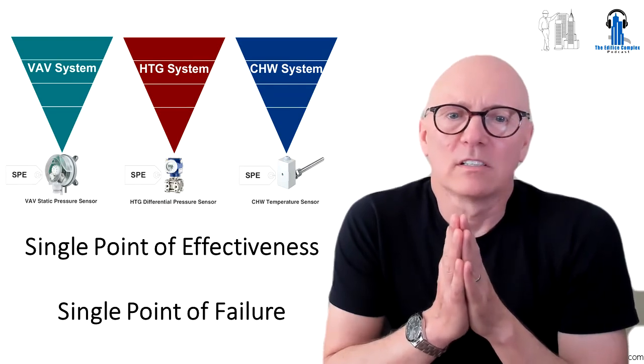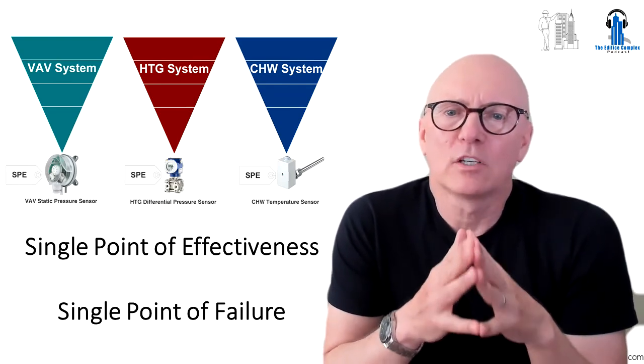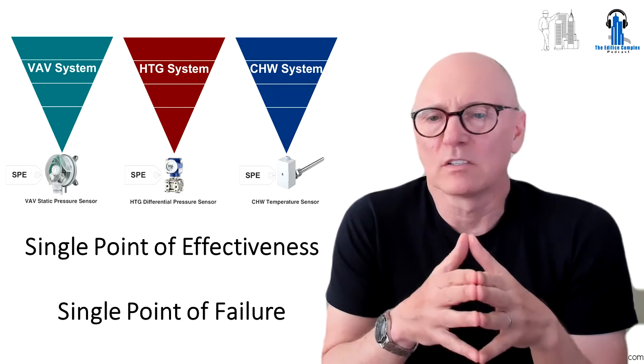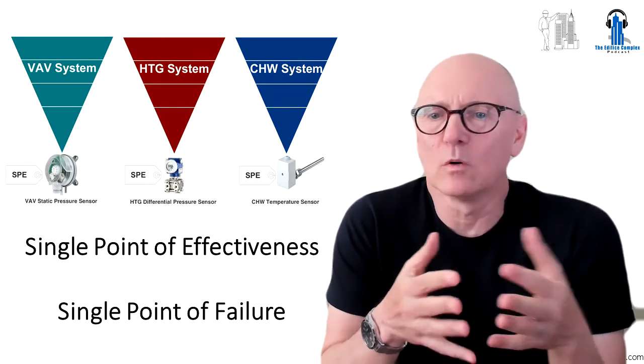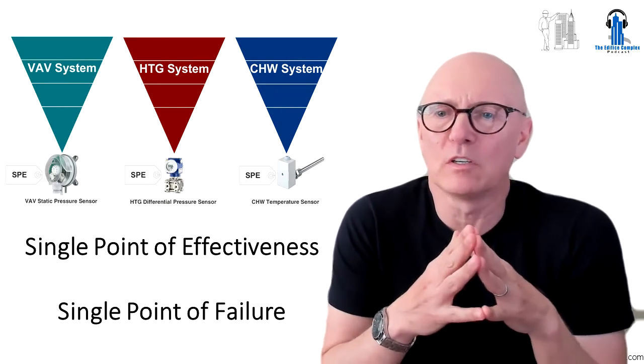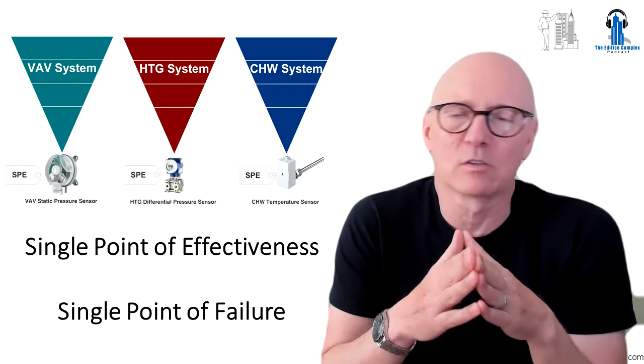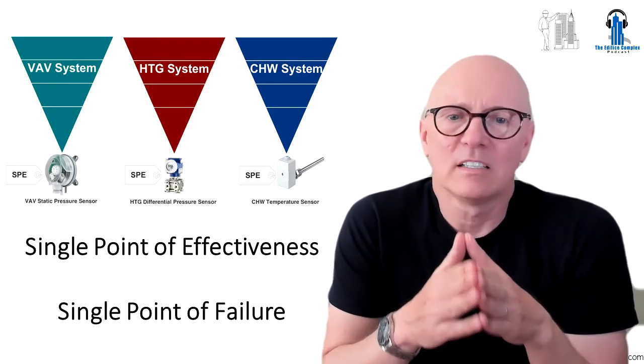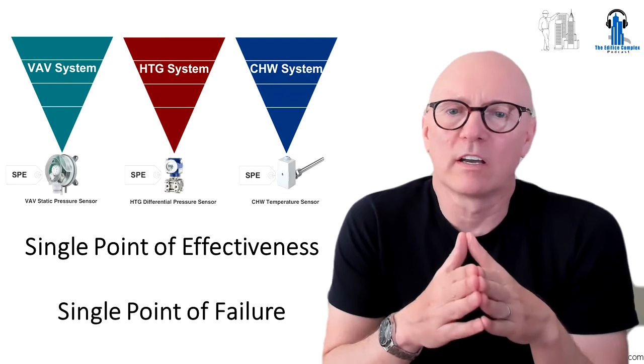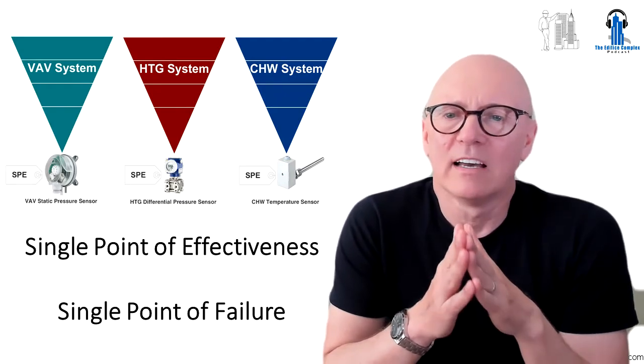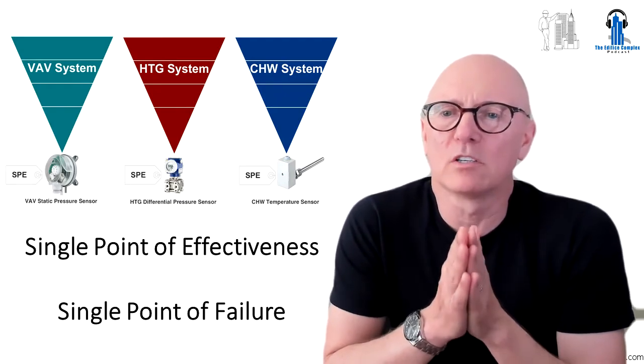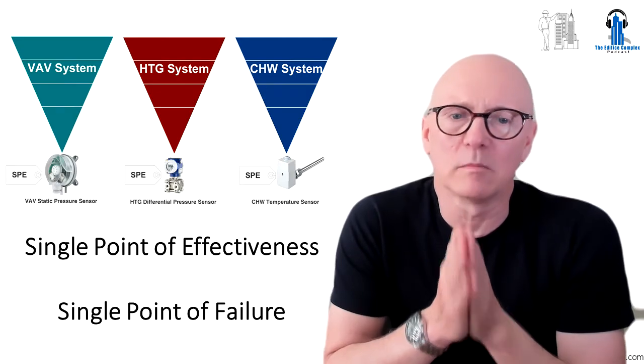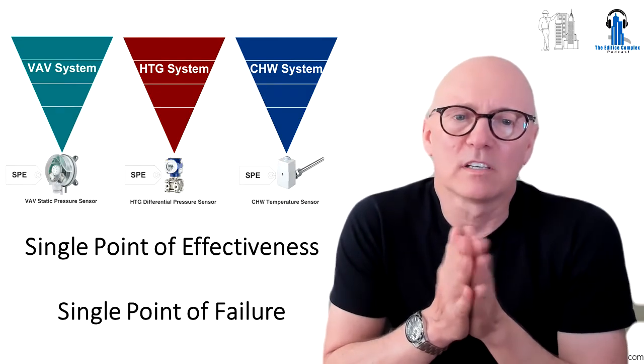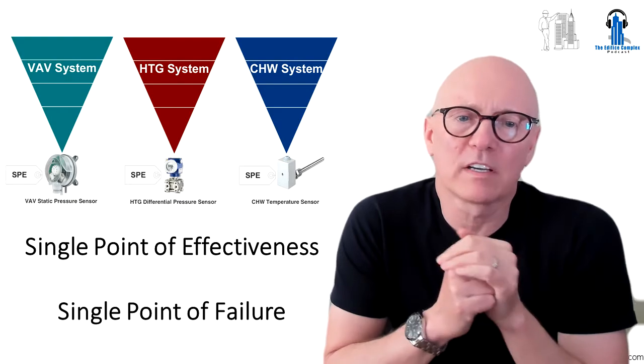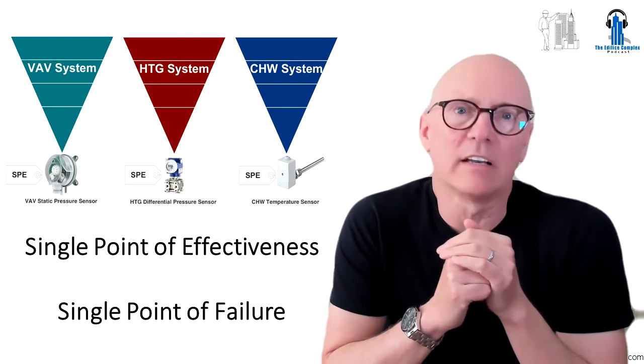The dirty secret is that most critical energy consuming systems, such as ventilating systems, VAV systems, heating, cooling, they rely on a single $250 device, such as a pressure sensor or temperature sensor. These devices have to be installed in the correct location, correctly calibrated, and the optimum set point empirically determined via field testing, aka commissioning. These devices are single points of effectiveness and also single points of failure.